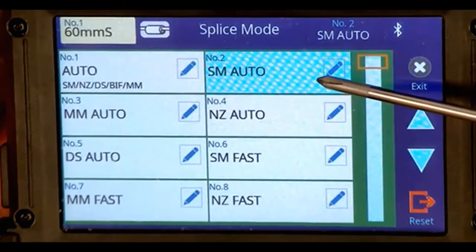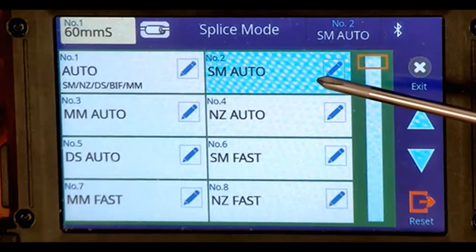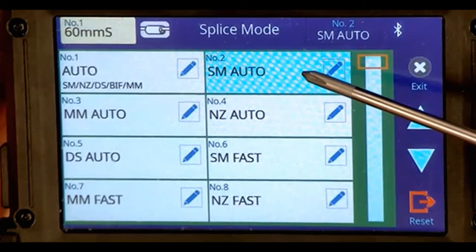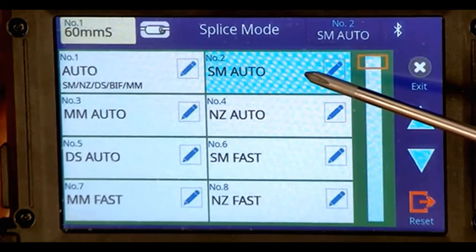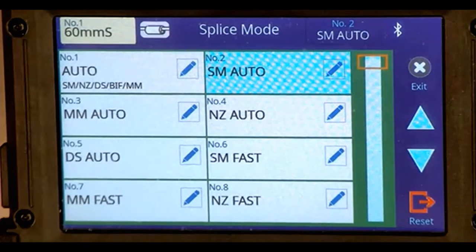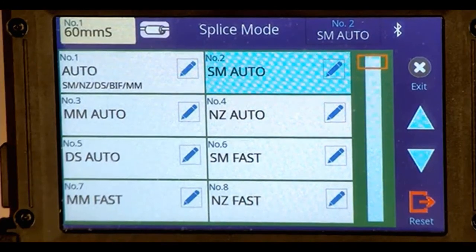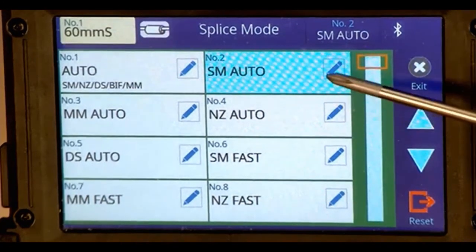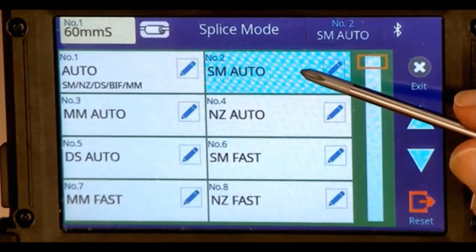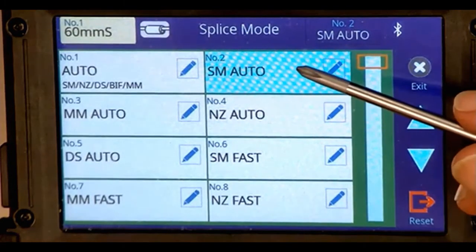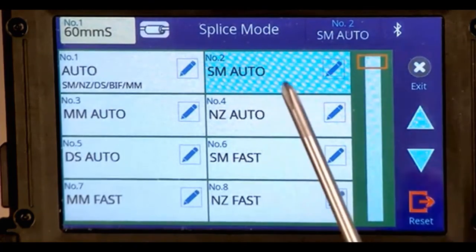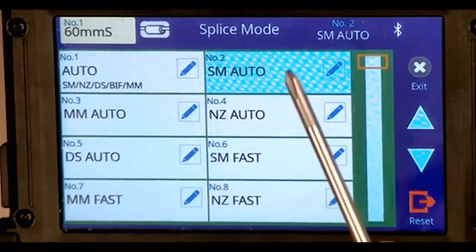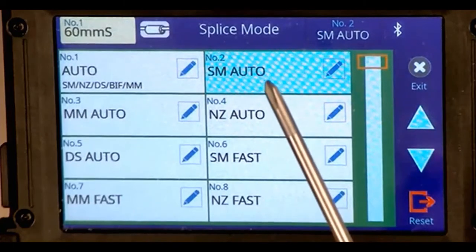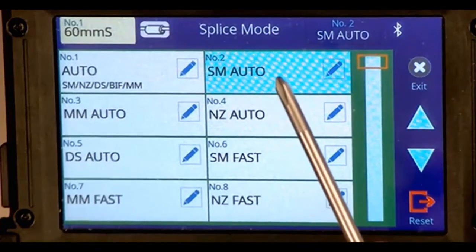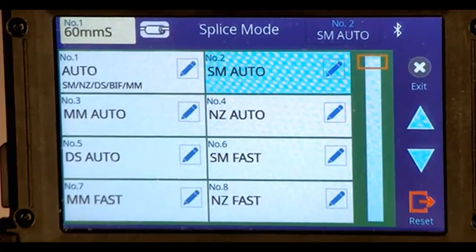Down here, you see SM fast. It is a little faster than this mode, but we don't recommend you use it because this is still plenty fast. And you've got plenty of other things to do when you're splicing. There's the heat shrink time. There's the time to prepare, strip, and clean the fibers. So you don't really gain anything. And what you lose is this does not use the glowing fiber image to recalibrate and use that auto arc calibration. So you're really better off using the auto mode. And you're probably best to use SM auto for any type of single mode splicing and multi-mode for multi-mode splicing.